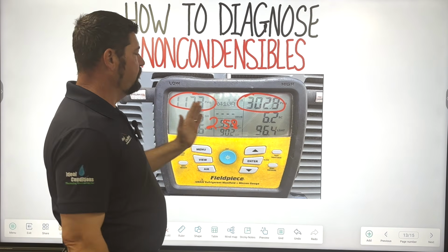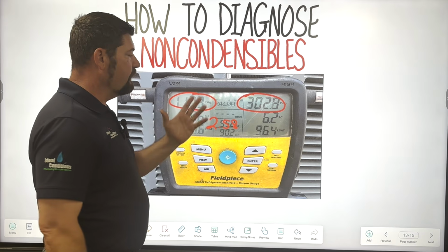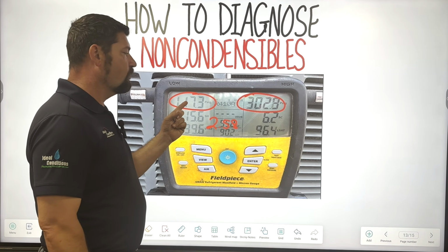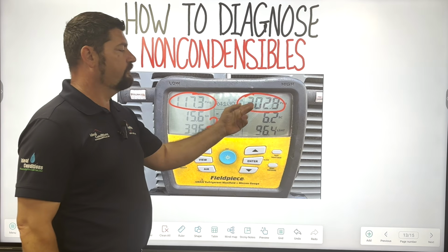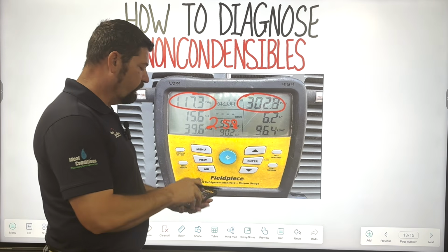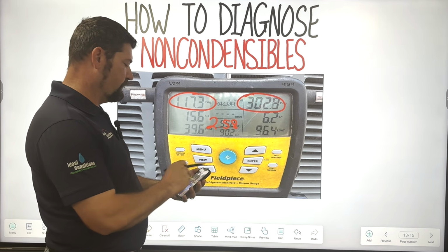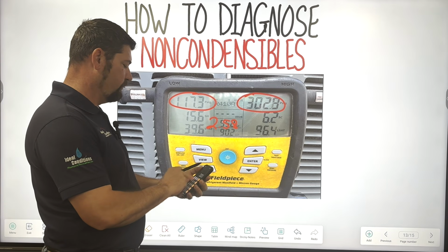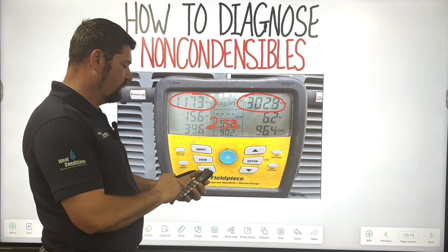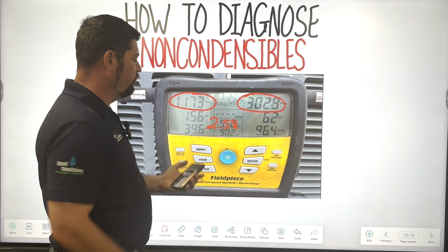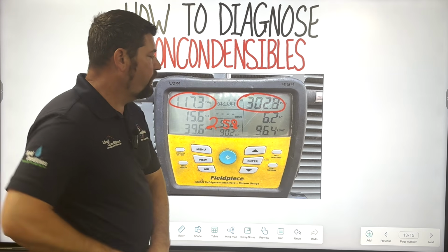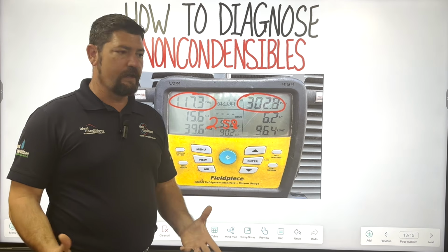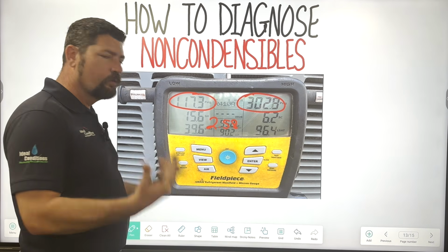That's a pretty solid pumping ratio. Now, in that video, we saw that this number got up to about 125, and we saw this number got up to around 320. And even if we looked at those numbers at their higher value, let's just say 320, divide that by 125, we still come up with a 2.56 pumping ratio. So our pumping ratio on our compressor is good. There's no concerns there. That's just a quick rule of thumb.